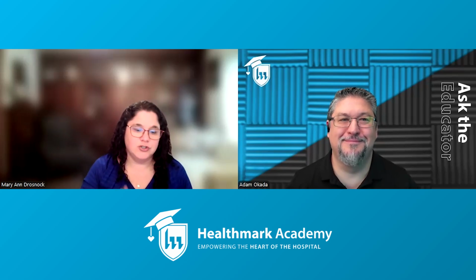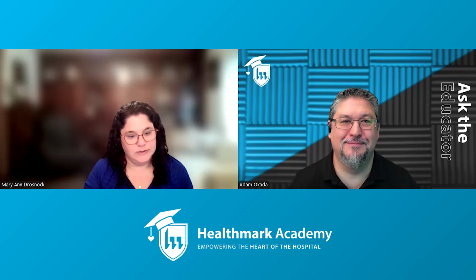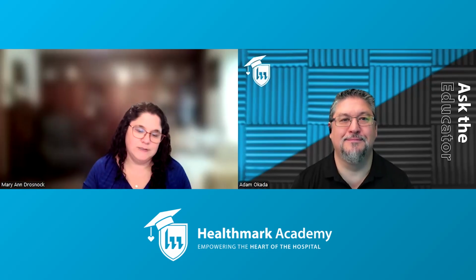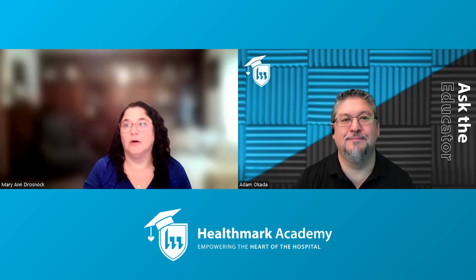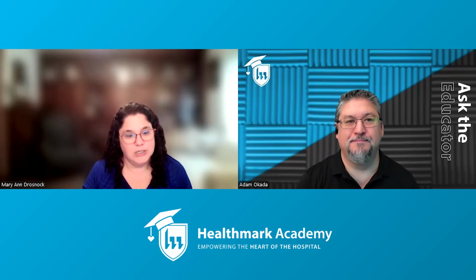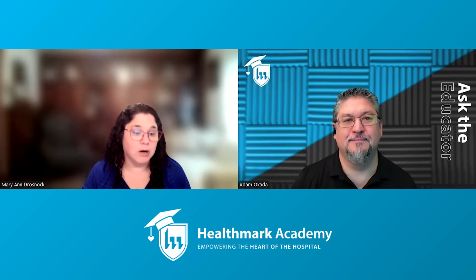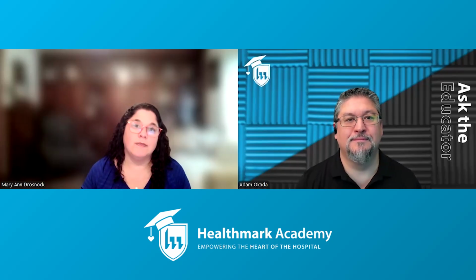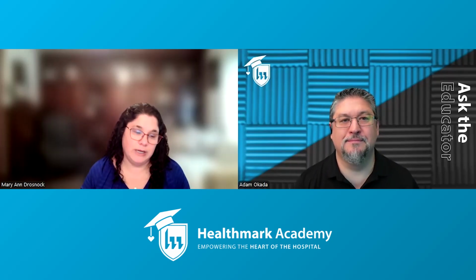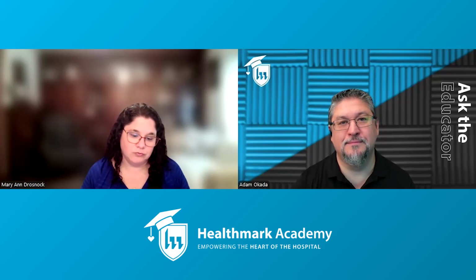They're meant to check for debris after cleaning to show that it can go on to the next step in the process. So that's a key factor I want you to keep in mind, because some people aren't really sure what this is about. It's a test for something like protein or ATP or a combination of different markers.